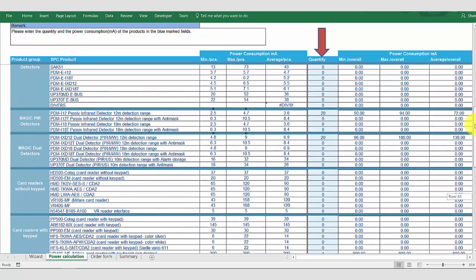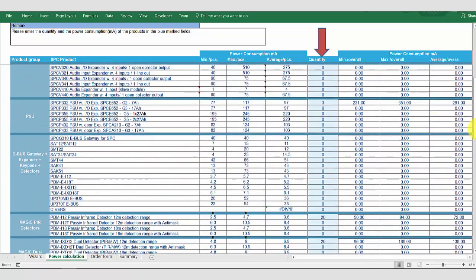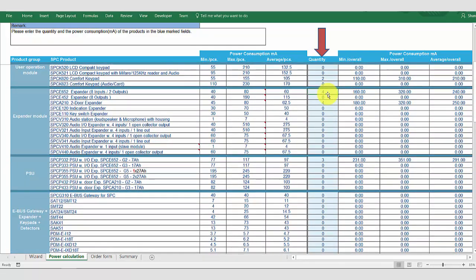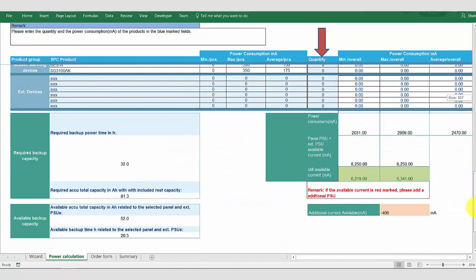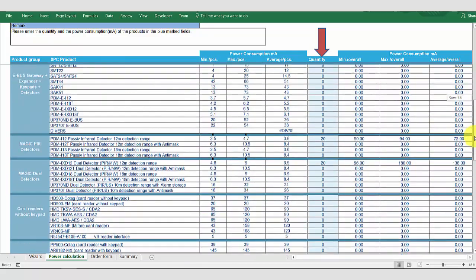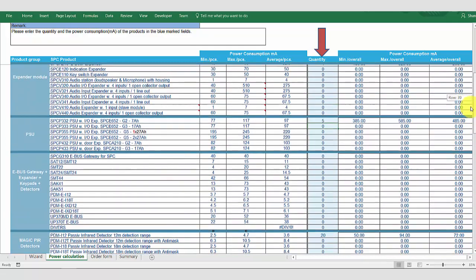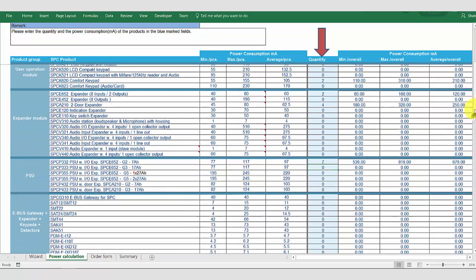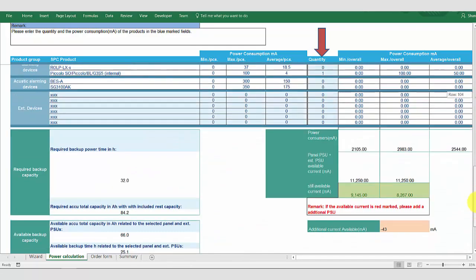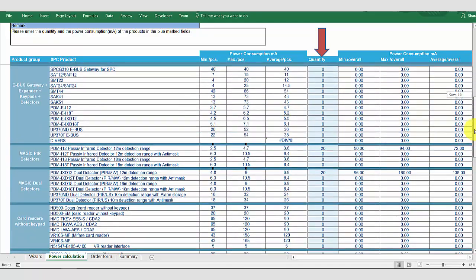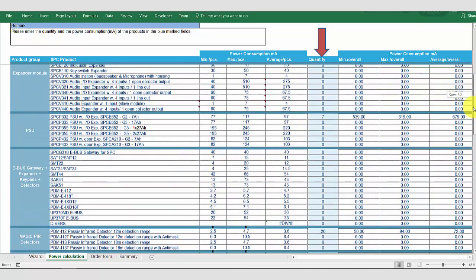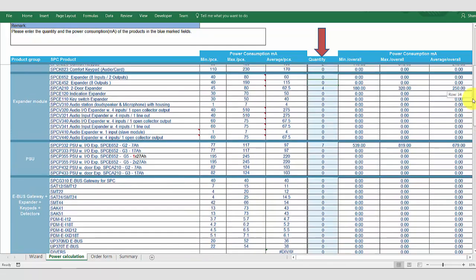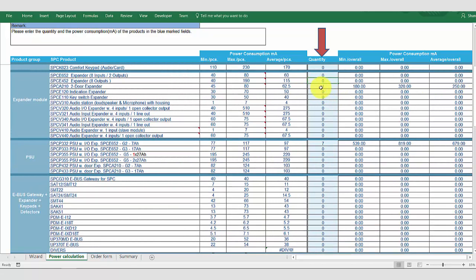So, we again change our input expander to be a power supply expander. We need additional power. So, what I'm going to do now is, as we've changed all our input expanders to power supply expanders, I'm going to change things around. Now, we can see here that we have four standard door controllers.